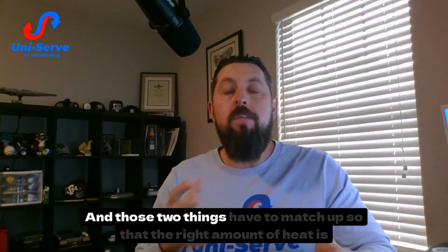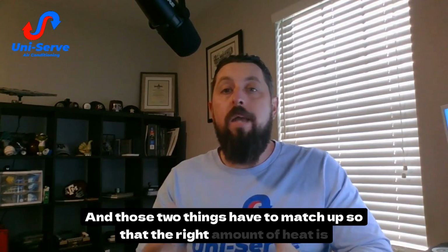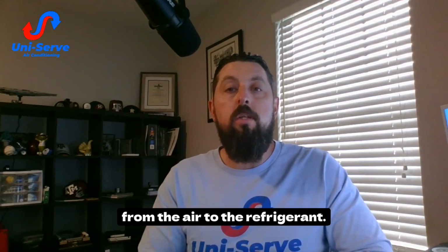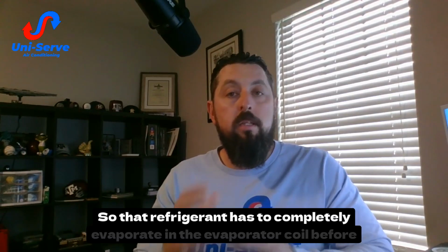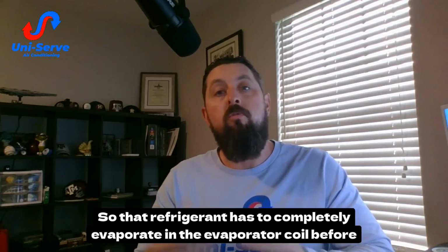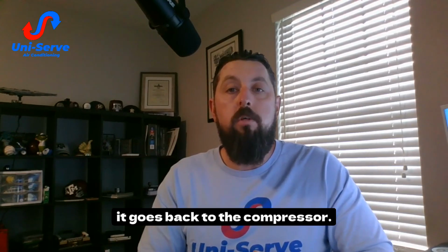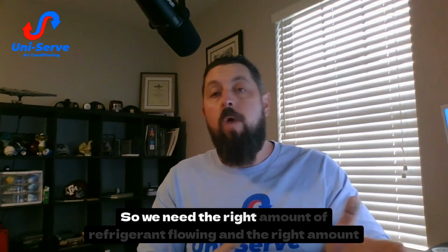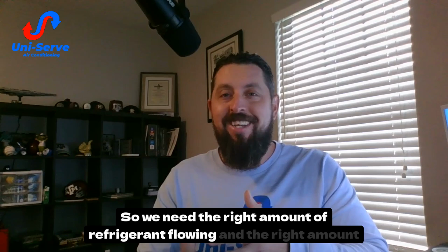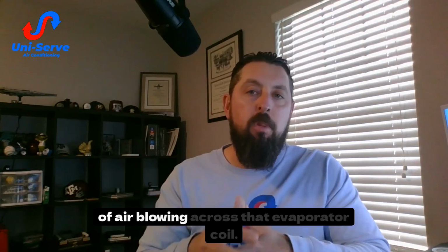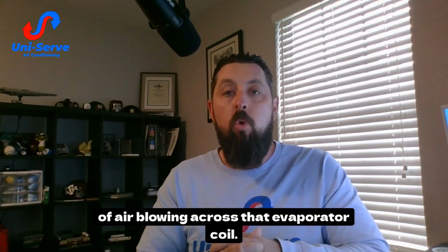Those two things have to match up so that the right amount of heat is transferred from the air to the refrigerant. That refrigerant has to completely evaporate in the evaporator coil before it goes back to the compressor. So we need the right amount of refrigerant flowing and the right amount of air blowing across that evaporator coil.